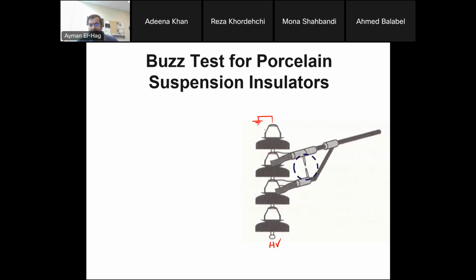You can look at it as a capacitor. So this is like a capacitor connected in series with another capacitor, in series with another capacitor, in series with the high voltage. So like 4 capacitors in series. Now, when you apply the high voltage, because they are in series, there will be a voltage distribution, more or less. Let's assume you have a similar voltage. There will be a slight difference, but assume you have here V, V, V, and V. So every one of those insulators is holding this voltage V.